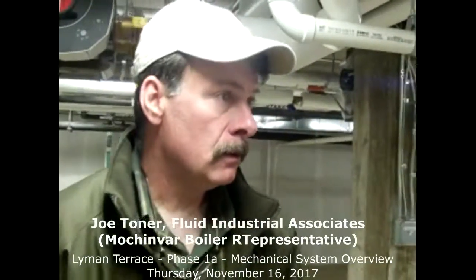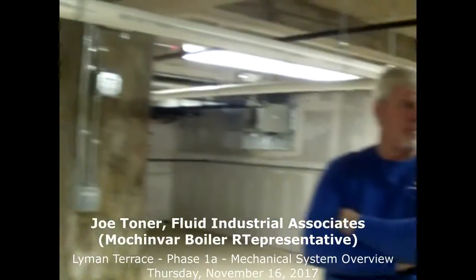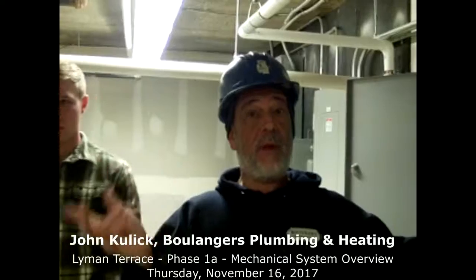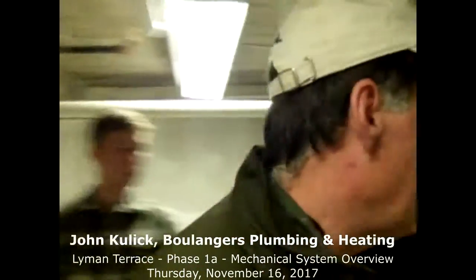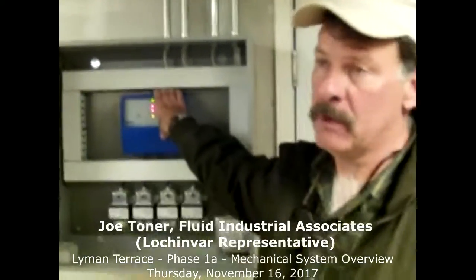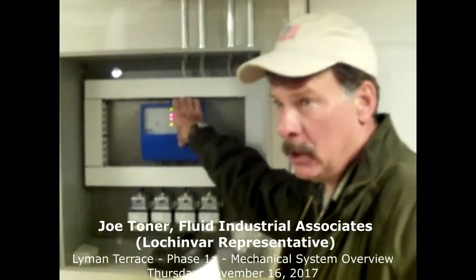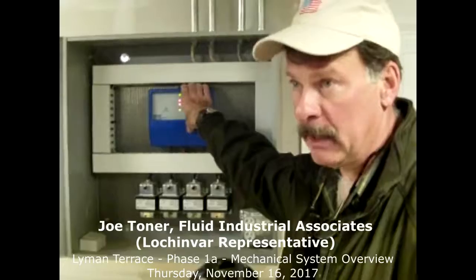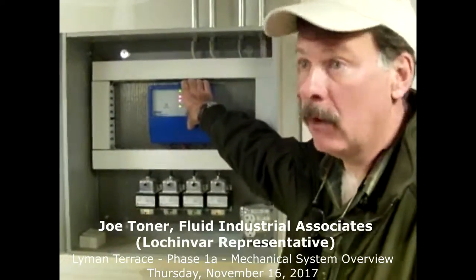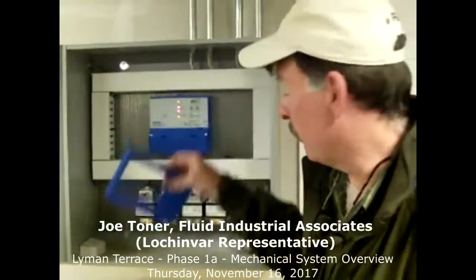So it's the same as the pump controller here. You need to visually look at this once a week, because you could have an issue with one of the pumps, you don't know it because you're not looking at a flashing code light. And then you come down and find, uh-oh, both of them are no good now. And just so you know, and I apologize if this is repetitive, you should know this. This box does two things. Number one, it will engage a second pump if the pump it's running is not running. They call that rotation, staging.